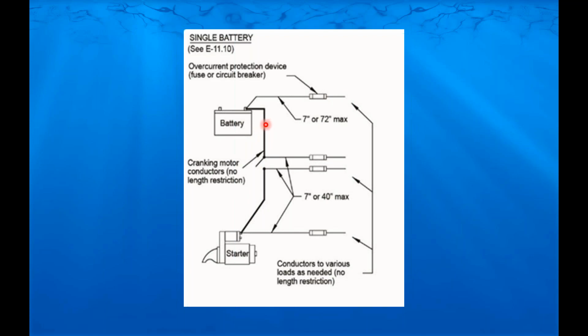The idea is if you have a place where you can get a switch in, you can get overcurrent protection there. And we'd much rather have the overcurrent protection first versus the switch. In this case, because of this circuit, you basically have 2 separate circuits coming off the same power source. You can have the switch here and then come off of that switch with the properly rated fuses for your auxiliary loads.